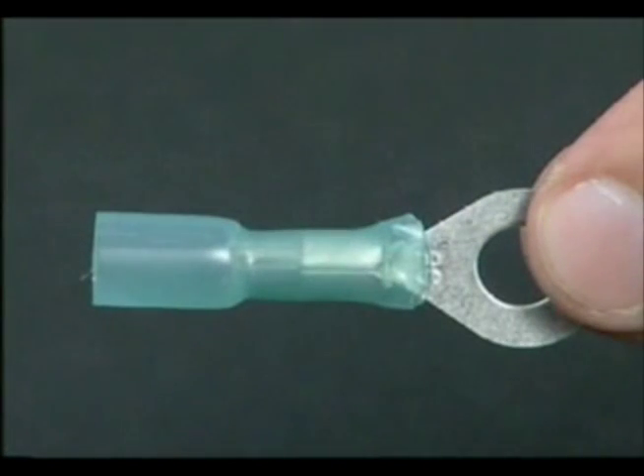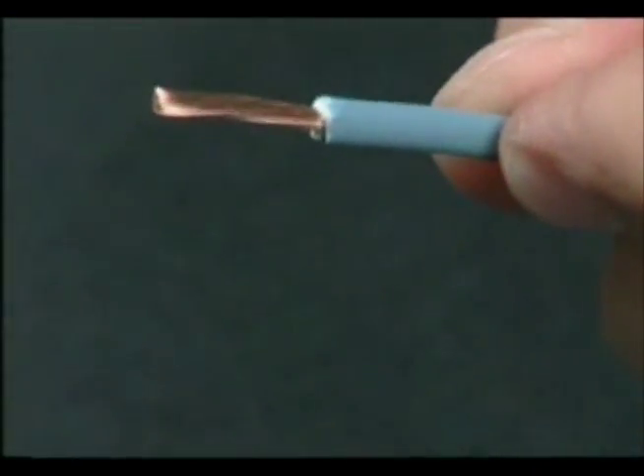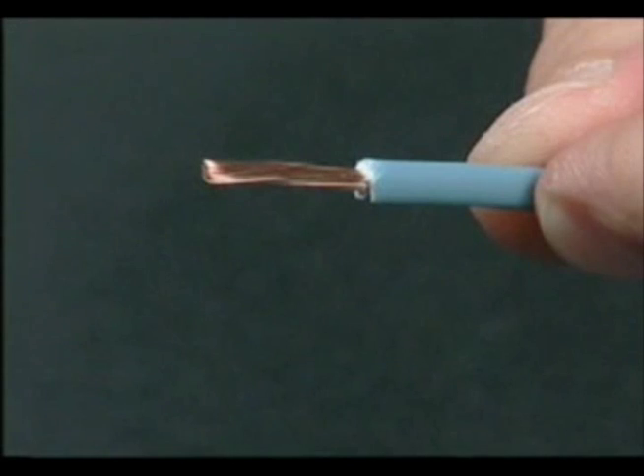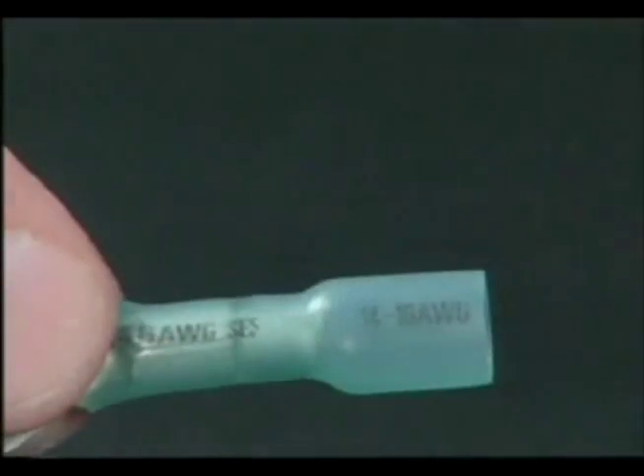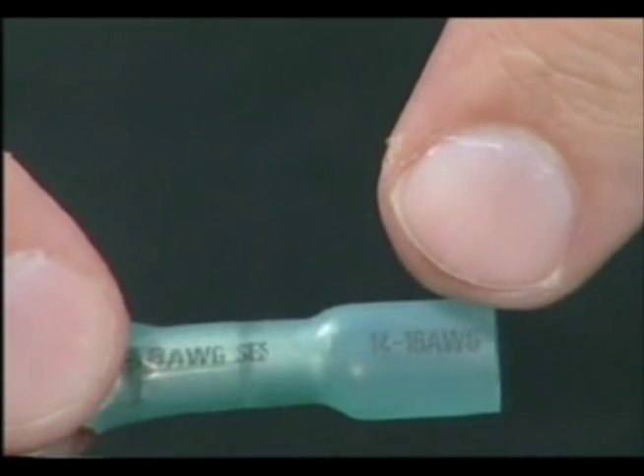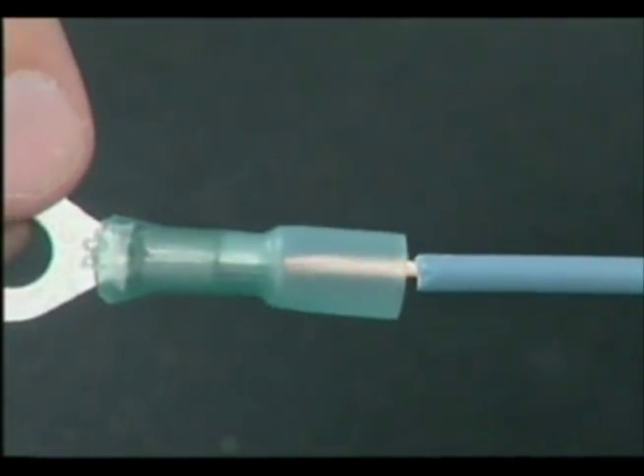To install sealed crimp and solder terminals, strip the wire insulation 1/2 of an inch. Select the proper sized terminal. Insert the wire into the terminal.